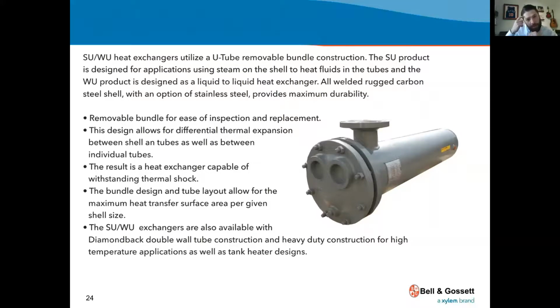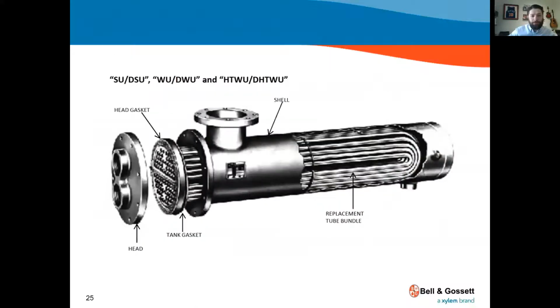The water is going to come in on the tube facing you. That's the tube sheet there. These are available in double wall tube construction. And we can also do high temperature. We can do some high pressure steam, but a lot of the time, guys, with these low pressure steam units, rarely do we see something over 15 PSI. We do a ton of these, 5 PSI, 10 PSI, but 300 pound pressure on the water side is not a problem at all.